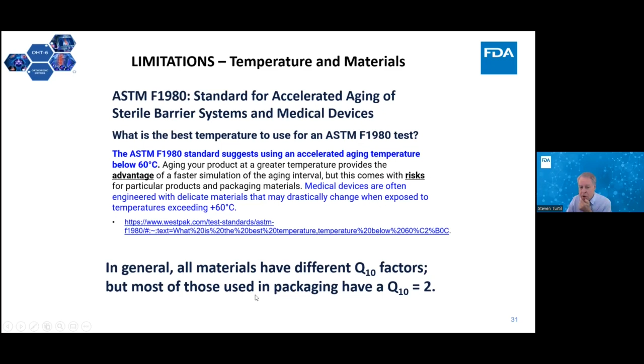And finally, an important addition here is ASTM F1980 standard suggests using accelerated aging temperature below 60 degrees. Medical devices are often engineered with delicate materials that may drastically change when exposed to temperatures exceeding 60 degrees. Here's the link for this. And in general, all materials have different Q10 factors, but most of those used in packaging have a Q10 equal to 2.